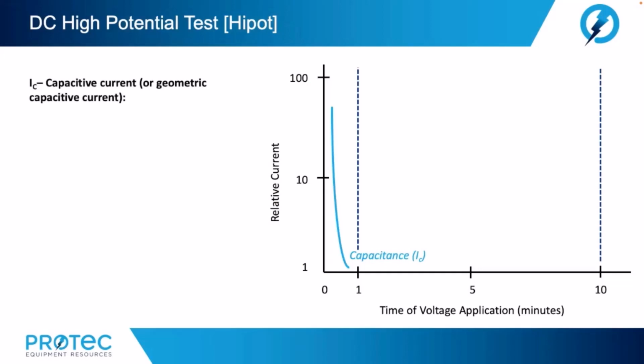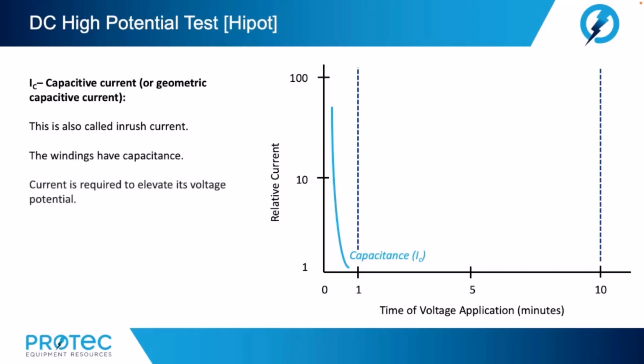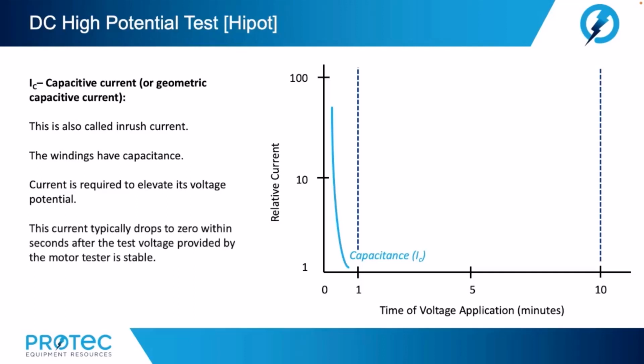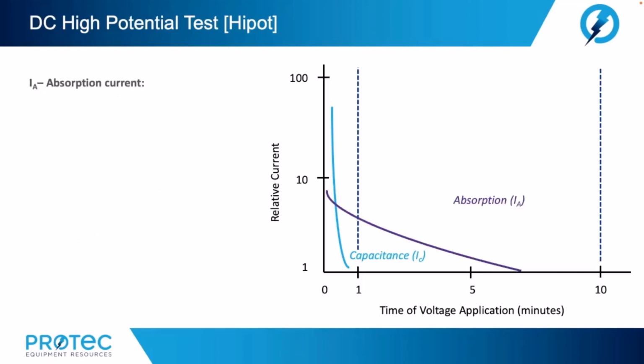All right, let's once again review those currents. Capacitive current or geometric capacitive current. This is also called the inrush current. The windings have capacitance. Current is required to elevate its voltage potential. This current typically drops to zero within seconds after the test voltage provided by the motor tester is stable.